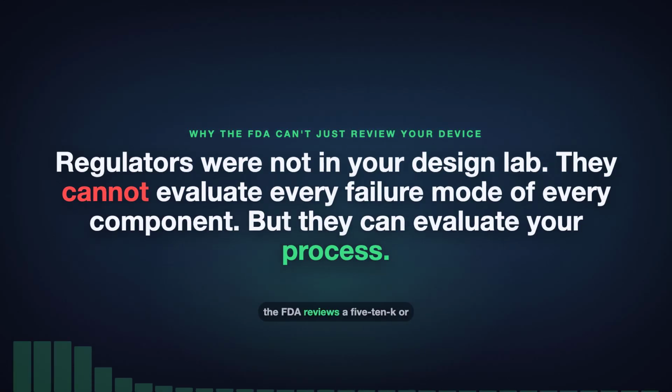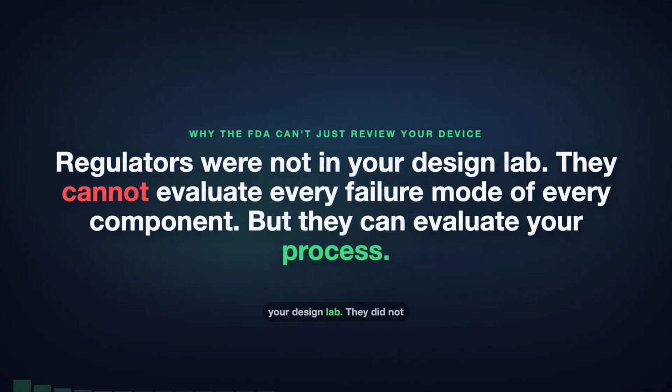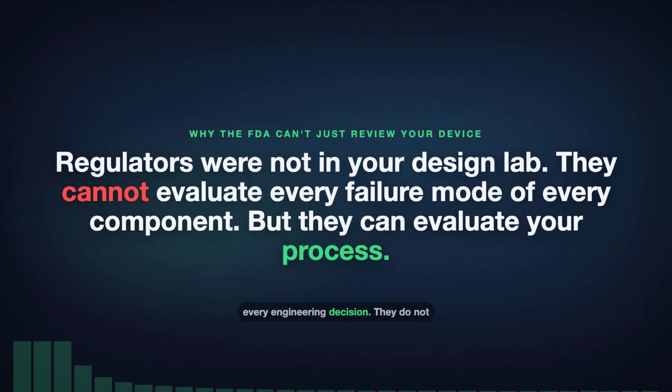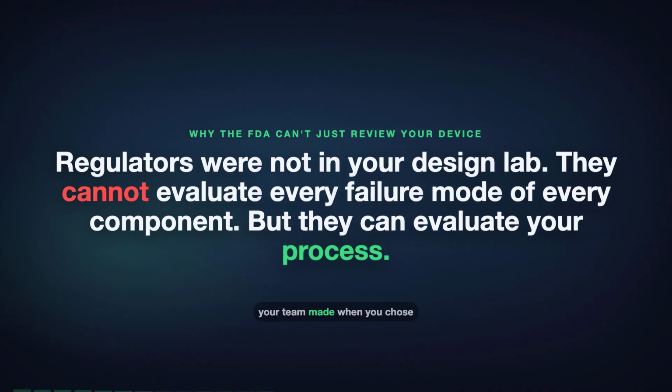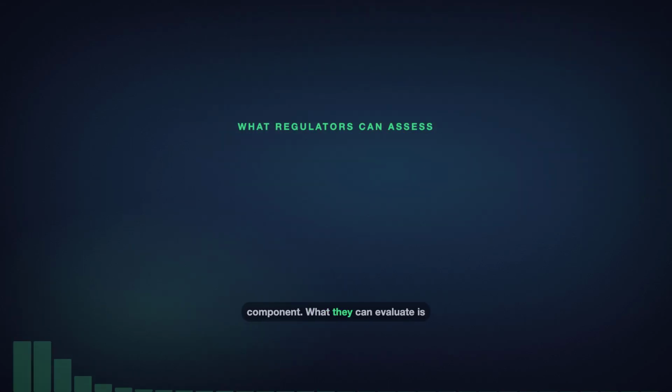When the FDA reviews a 510K or a PMA, they have thousands of pages of documentation. But they were not in your design lab. They did not see every engineering decision. They do not know the assumptions your team made when you chose that specific microcontroller. They cannot evaluate every failure mode of every component. What they can evaluate is your process.